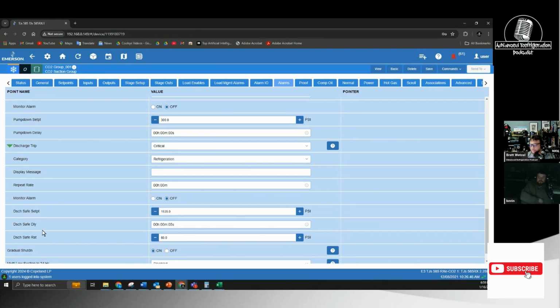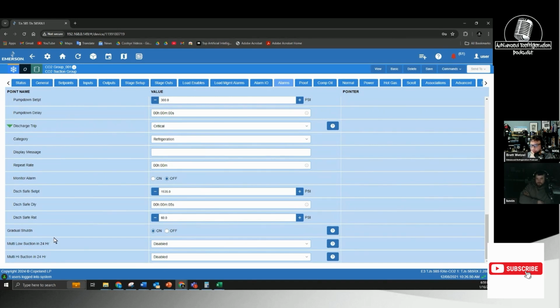Or in dryer shells, or dumping a flash tank. Yeah, those are the only times you're gonna make some dry ice. Even dumping a flash tank, it's hard. Really? So when you dump the flash tank, how are you? Because I know you try to stow as much when you're doing a pump down. So if you got to work on the flash tank, I know that you usually run the head pressure up just like you would on a regular conventional system, right? And then I just blow. Go ahead. I just blow it into the, or put as much in the gas cooler as I can, valve it off, and just blow it.